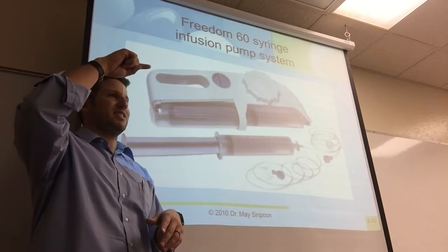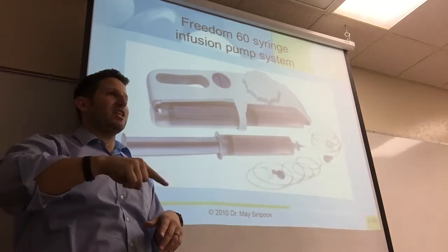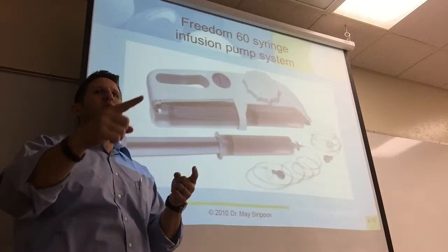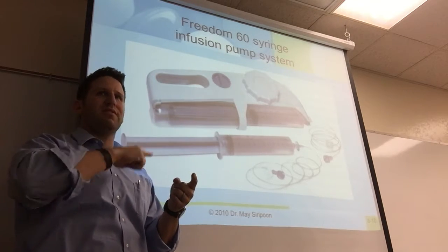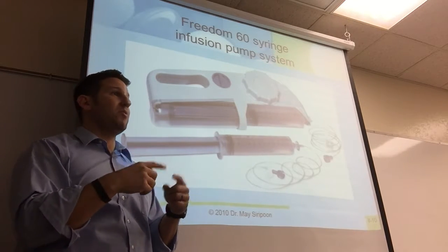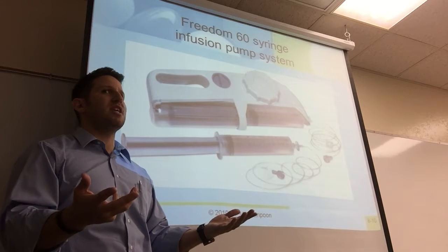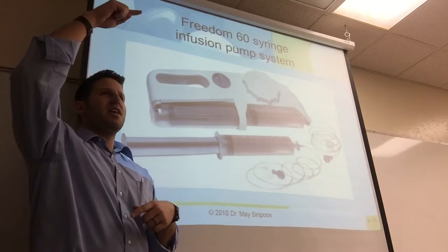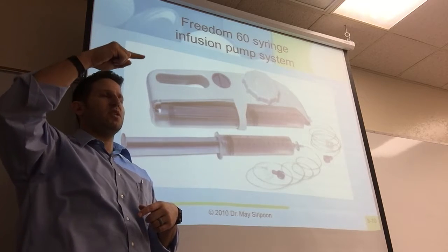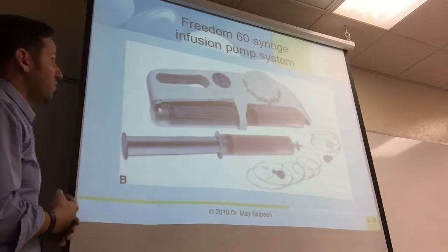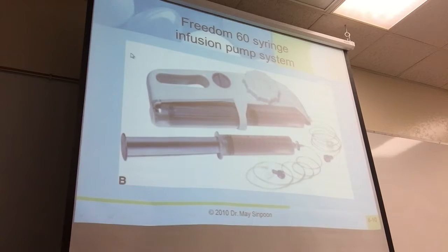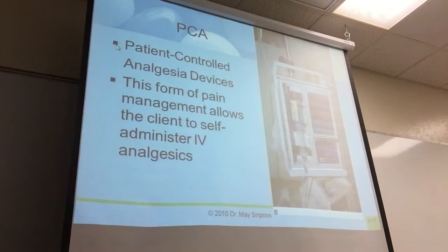And as it resets to go back to the top to push down again, it's getting bolus and then starve, bolus and starve, when it comes to drips, which can make an unstable patient. So that's why they put it on the neonate patient, because it's a gear set that has a nice continuous flow that's very good for the patient. So there are important reasons, and different patient populations, for why we use these modes of medication administration.